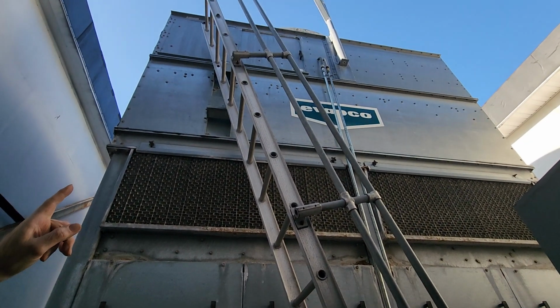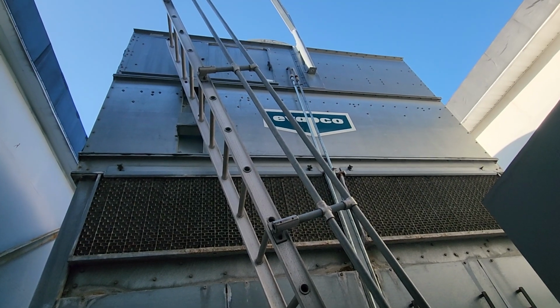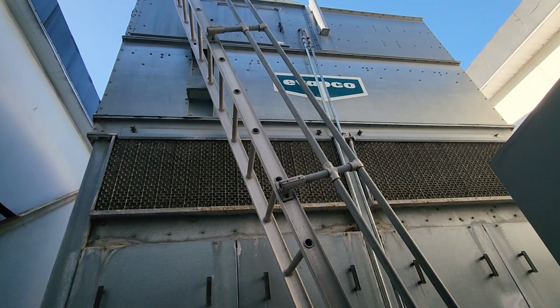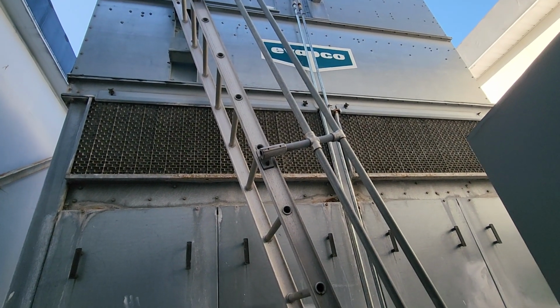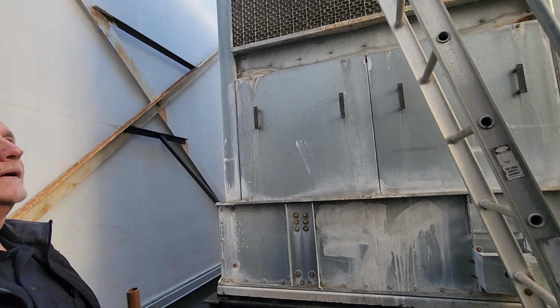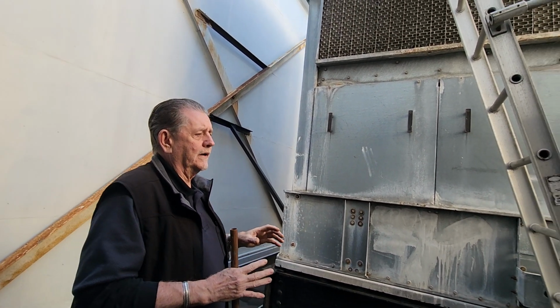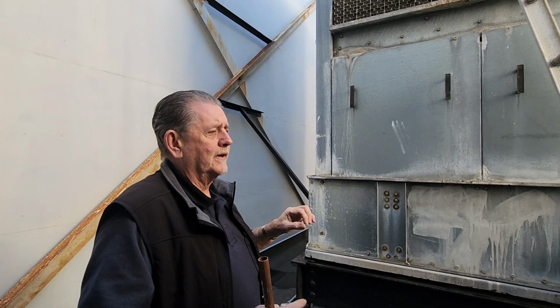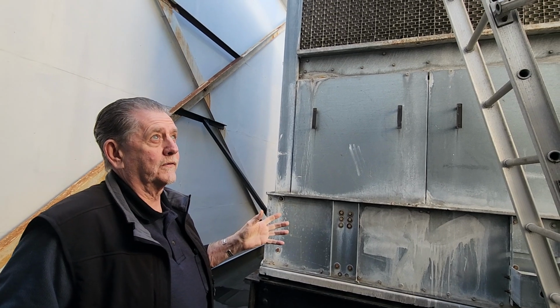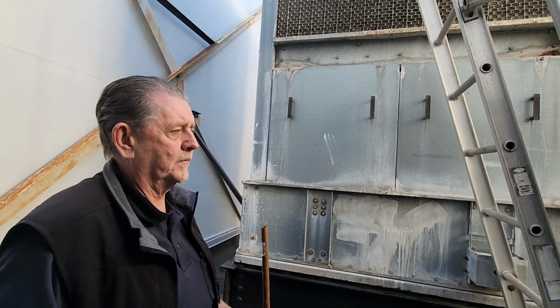There is also a fan at the top of there. That fan is huge. It takes up the whole top section. In this particular building, because they didn't have water treatment the first 6 years, we replaced the whole upper chamber, including the door. That's how bad the water treatment was. Wow. It was just not done. And that's not anything that will say that there was bad management or anything on that line. We took over the building from the builder after about 6 years, and I insisted we get water treatment, which is right now we've been running for 10 years since then, with no issues with anything needing to be replaced because of rust and bad treatment from the water.